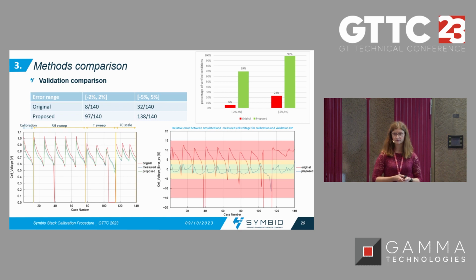Have you studied the root cause why some of these cases failed? Some of the cases failed mainly during dried cases, so it's either high temperature or low humidity cases. That's why we want to calibrate it also with varying operating conditions, because here we have a huge difference between the operating condition in which we calibrate it and the real operating conditions. About 20 degrees difference, that's why.